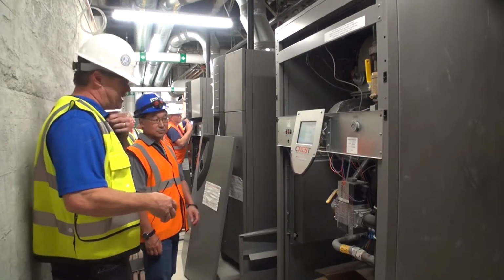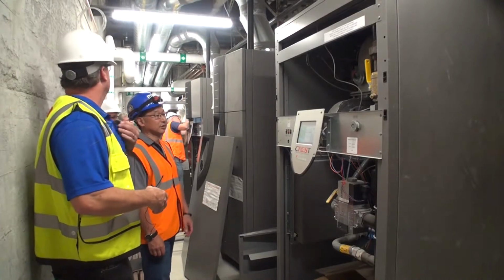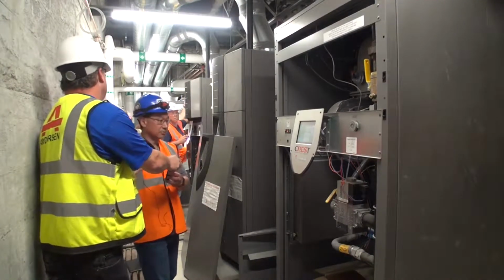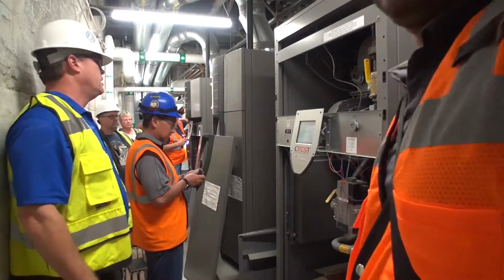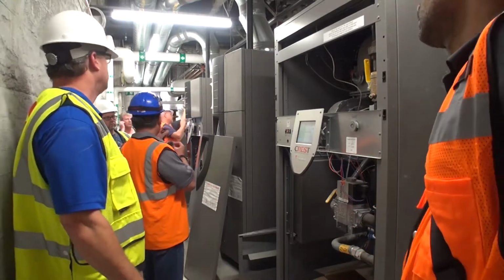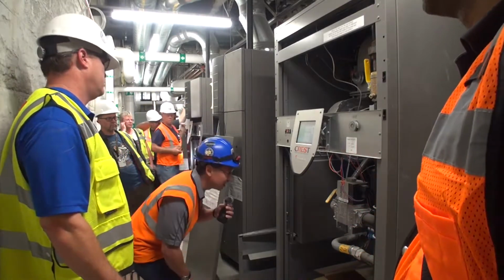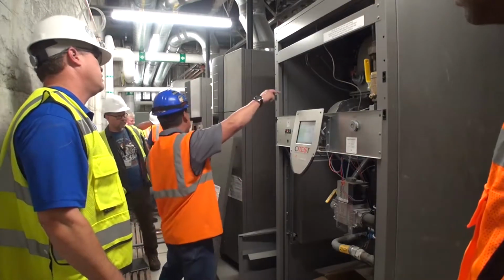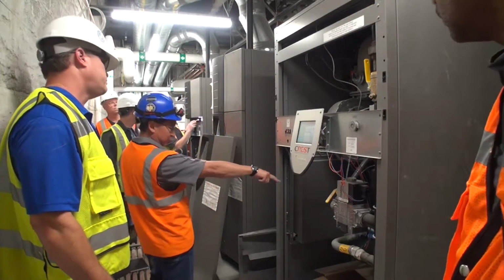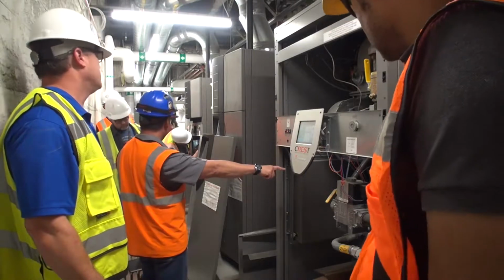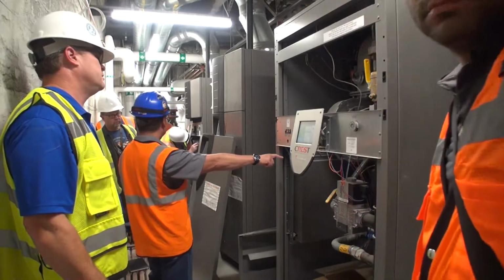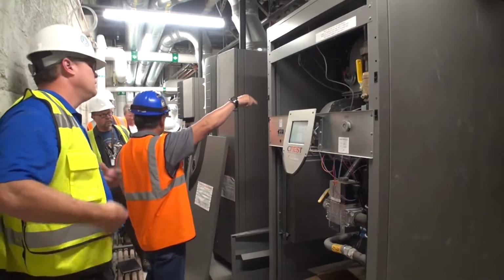I think the controls will be more important. Where is your pilot and flame sensor? The pilot and flame sensor are actually inside, if you look you can't really see it, it's way in the back and the top. So this black portion back here that looks like a 55-gallon drum is your heat exchanger. Your flame sensor and igniter are sitting up on top.